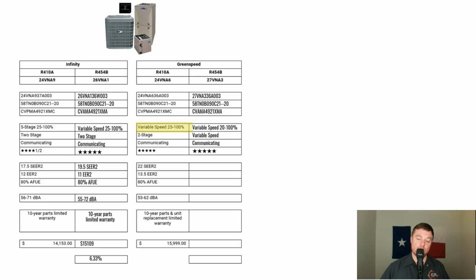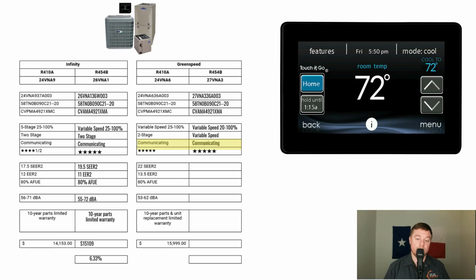Now going to the operations of the system, the 24 VNA6 is fully variable and can operate anywhere in between 25 to 100% cooling capacity, and it can adjust in 1% increments. Now for the 27 VNA3, it can operate in between 20 to 100% cooling capacity, so slightly lower and better than the R410 equipment. Now the 24 VNA6 is utilizing a 2-stage furnace, and the 27 VNA3 is technically variable speed in heating mode because the primary source of heat is the heat pump, and the furnace is only acting as emergency heat.